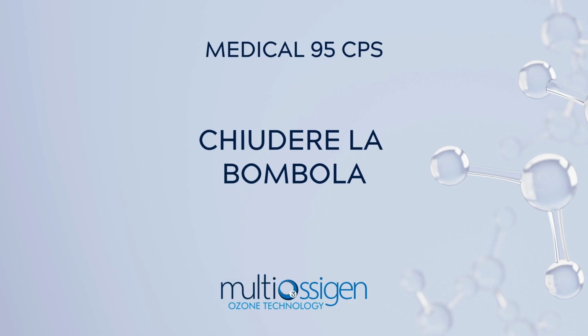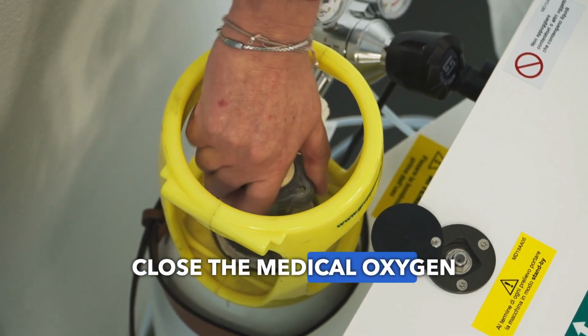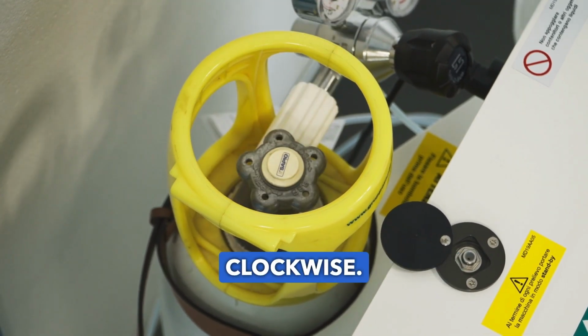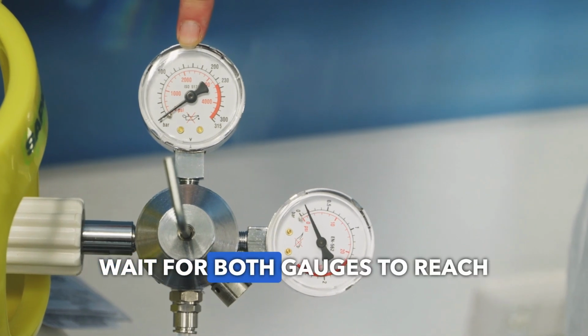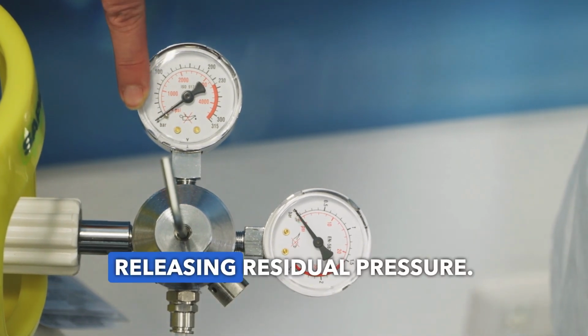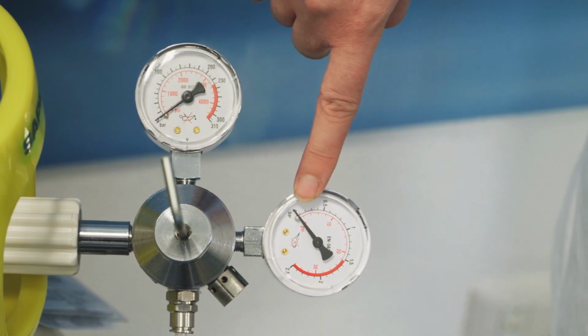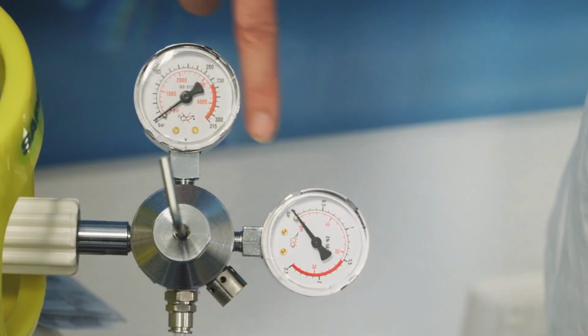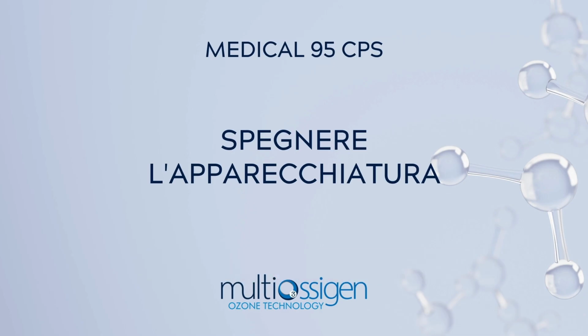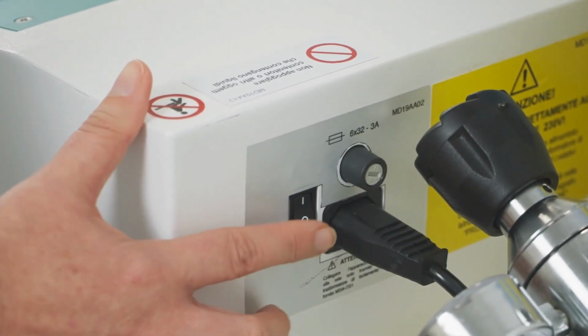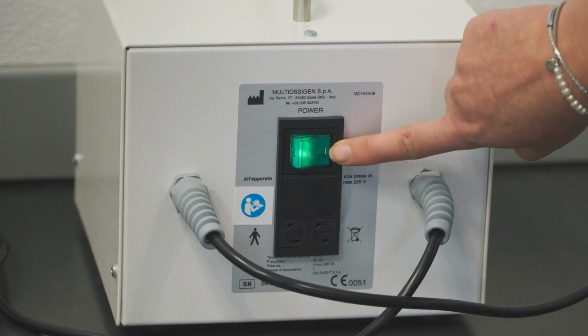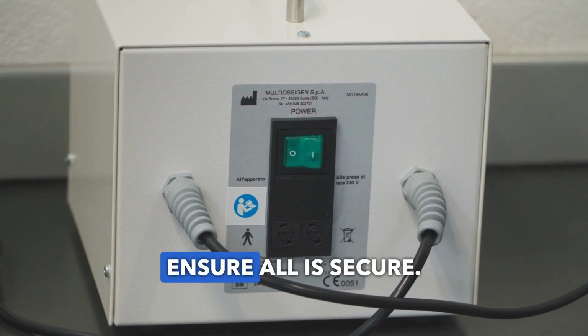Close the cylinder. At day's end, close the medical oxygen tank by turning the valve clockwise. Wait for both gauges to reach 0, releasing residual pressure. Power off the equipment. Turn off the device from the back, then the isolation transformer. Ensure all is secure.